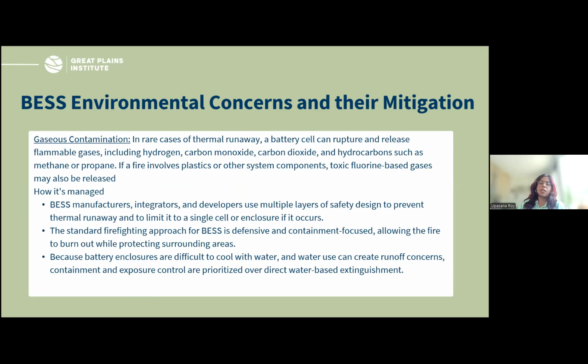Another concern related to thermal runaway is gaseous contamination. Since the batteries are placed in racks, the first thing that happens is usually gas starts building up. When that gas builds up, there's a detector within the container system that triggers it to open and let the gas escape. I believe around 14% of the total accumulated gas triggers the opening of the container, and that gas gets dissipated into the environment.